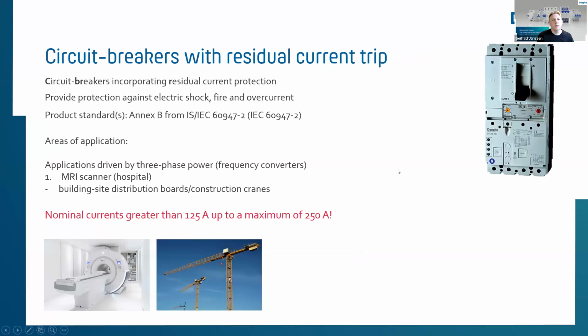The third product to be mentioned are circuit breakers with a residual current trip. And the application is if we have currents greater than 125 amp, those, let's say, big breakers do the same job like the ones before, provide protection against electric shock, fire, and overcurrent, but up to 250 amps. And the main application for us, as experience, are MRI scanners all over the world, and as well construction sites. For example, the company Philips recommended some of those breakers for their MRI scanners around the world.